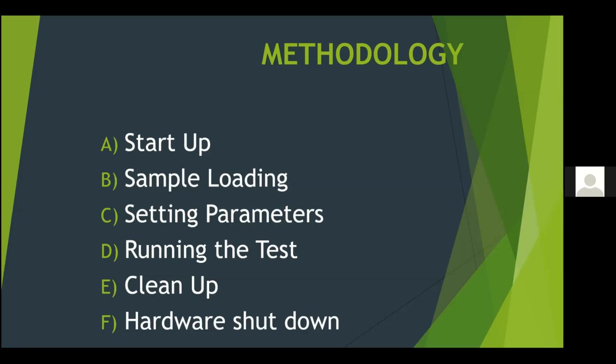The first step is the DSC was opened by pressing the lid button on the touch screen. Second, forceps were used to carefully place the sample pan and empty reference pan on the two pedestals. The empty reference pan should be placed on the rear pedestal and the sample pan on the front pedestal. The third step is the lid button on the touch screen was pressed to close the machine.